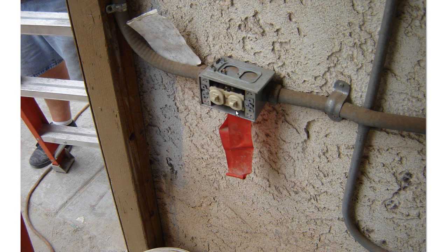Here's the switch, and it's a stack switch. If you shut one of those switches off, it killed the motor, because it was only providing 110 to the motor. But the problem is that the power will go through the windings of that motor and come back through, so it's an electrical shock hazard at the switch as well as the motor itself, because both circuits, both phases, are not disconnected. That's what we need to pay attention to here. That's why we install a double pole single throw switch, to disconnect both phases, 110 each, to provide 220 to a swimming pool motor. And we're not talking amperages or anything here. This picture's kind of dark, but let's go on to the next one.